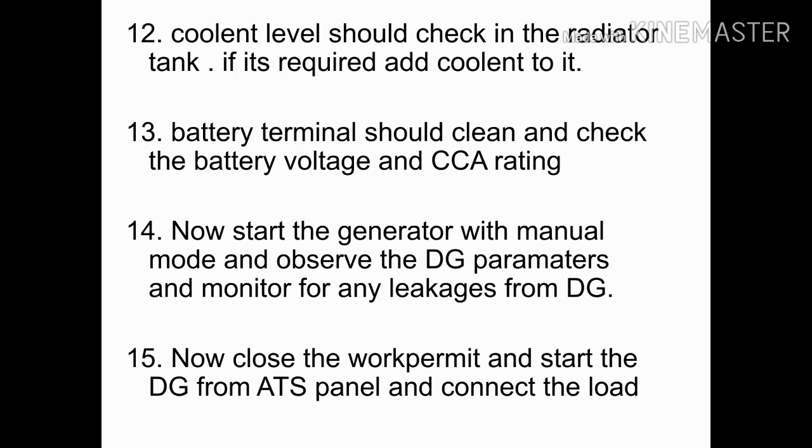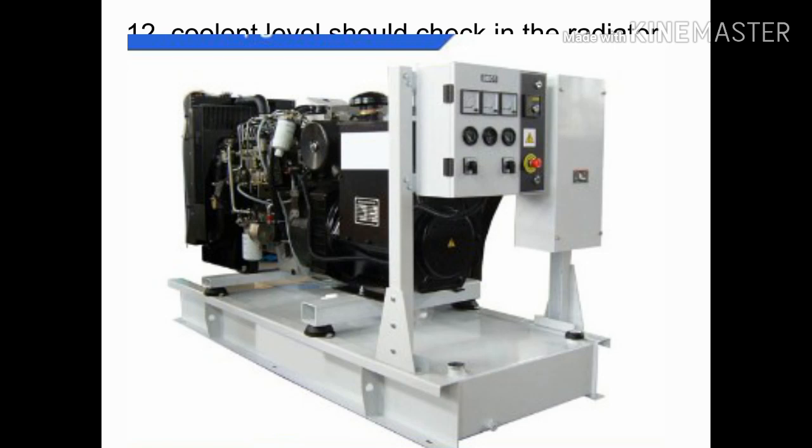These are the steps for normal periodic maintenance of the diesel generator. After completing them, start the generator in manual mode and run it for 15 minutes. Observe the DG parameter readings such as speed, pressure, and voltages. Check for any leakages from the oil tank, water separator, and coolant system. If everything is found normal, switch off the DG, close the work permit, then start the DG from the ATS panel in auto mode and reconnect the load to the supply.